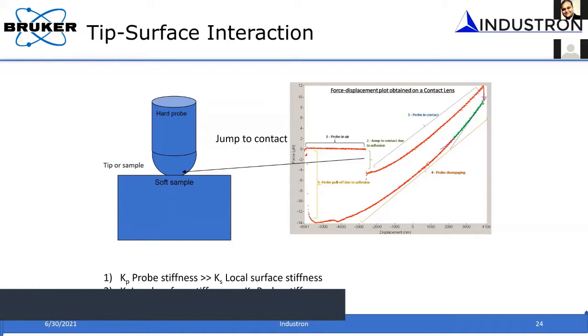We ignore the adhesion part, but here you can't do that because the adhesion forces are almost comparable to the forces that you are applying. And you're talking about the length scale, in this case from the point of contact to the maximum load, of about 5 micron. So even for small forces like 12 micronewton, the displacement range is about 5 micron. So normally for soft biomaterials, this is what happens.